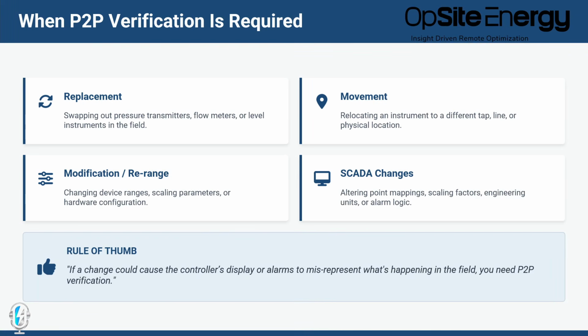Got it. So if we're going to focus on thorough, you can actually go to that next slide where it's got your, when the point-to-point verification is required, because it really speaks to when, what thorough even means. And you've got these categories. You've got number 1, when there's a replacement. When you're doing a pressure transmitter, flow meter, does that include anything like or kind equipment? Yes. So even on replacement for like and kind, you still want to do that point to point. Yes, and again, you're going to have your own procedure, and you're going to write how you handle your point to point.